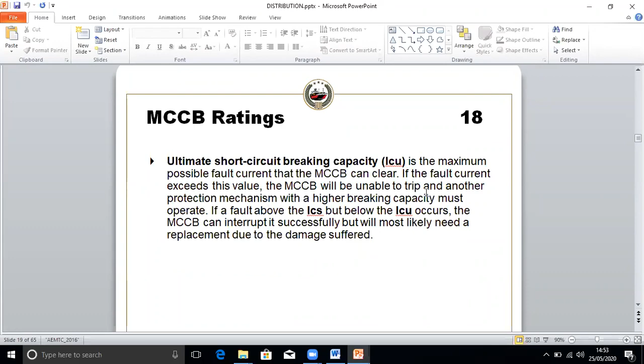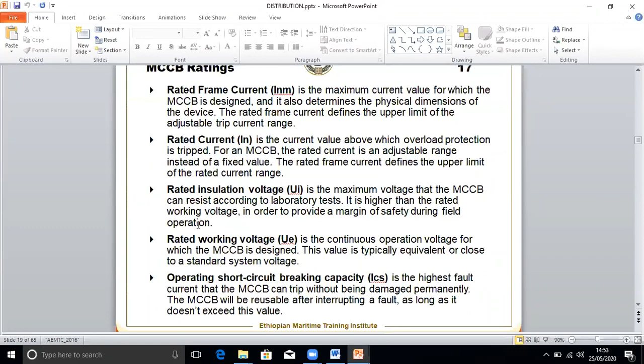Ultimate short circuit breaking capacity, written ICU, is the maximum possible value of current that the MCCB can clear. If the fault current exceeds this value, the MCCB is unable to trip and another protection mechanism with a higher breaking capacity must operate. So where we use this MCCB, we use it as the feeder circuit breaker.